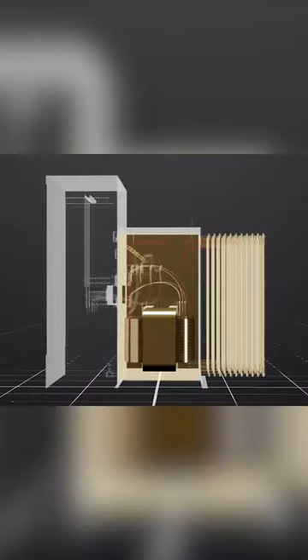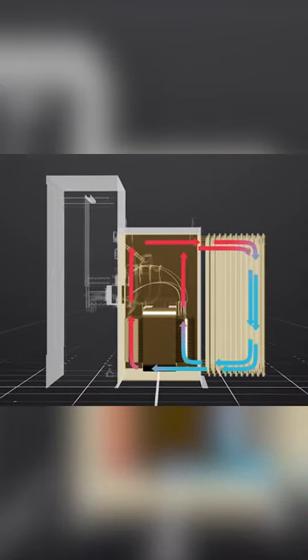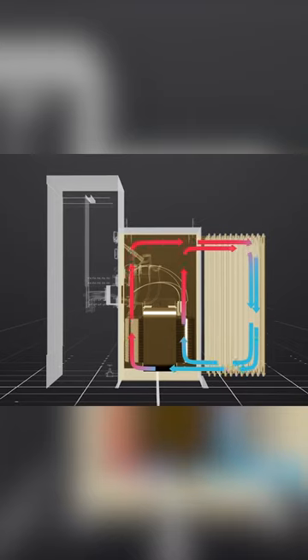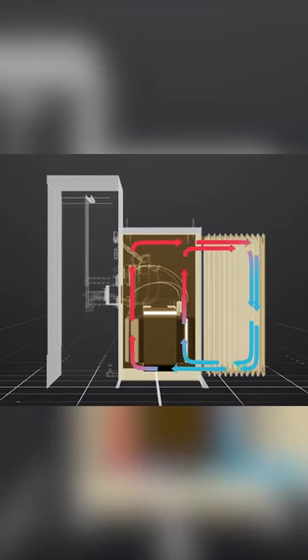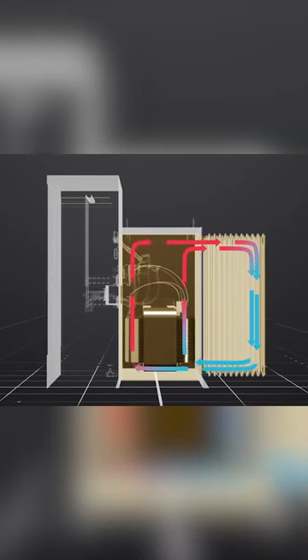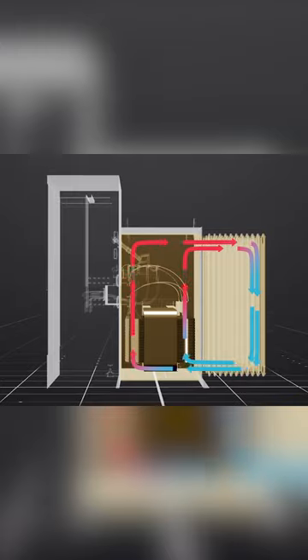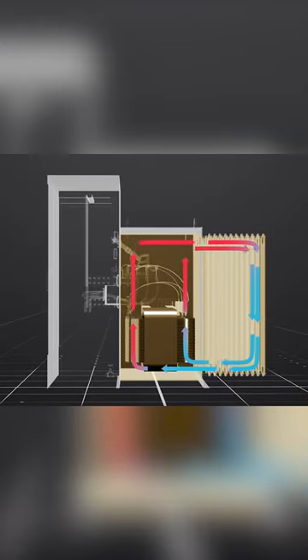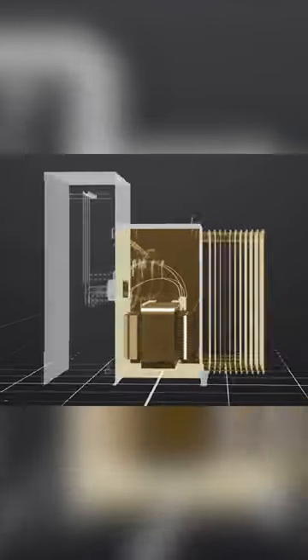As the fluid rises in temperature, it rises to the top of the tank. It enters the radiators where the ambient temperature cools it off. As the fluid cools, it drops to the bottom of the radiators and re-enters the tank. This process is called natural convection.